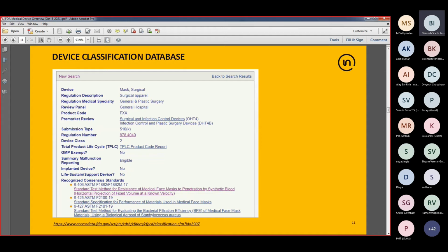You need to do your due diligence when you are submitting a 510K to FDA by comparing your product, your proposed device, against a predicate device and checking the predicate details that are available on the FDA website. A lot of times that tells you what standards need to be complied with, what kind of testing is needed to satisfy FDA requirements. Nonetheless, you will find some recognized standards mentioned by FDA. More often than not, these are all special controls, basically specific performance related standards rather than general standards that are mentioned.